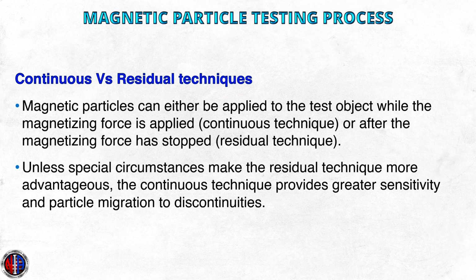Continuous versus residual techniques. Magnetic particles can be applied to the test object while the magnetizing force is applied, meaning the continuous technique, or after the magnetizing force is stopped, the residual technique. Unless special circumstances make the residual technique more advantageous, the continuous technique provides greater sensitivity and particle migration to discontinuities.